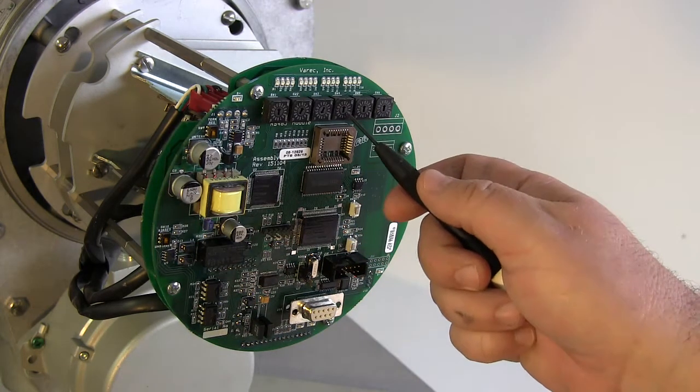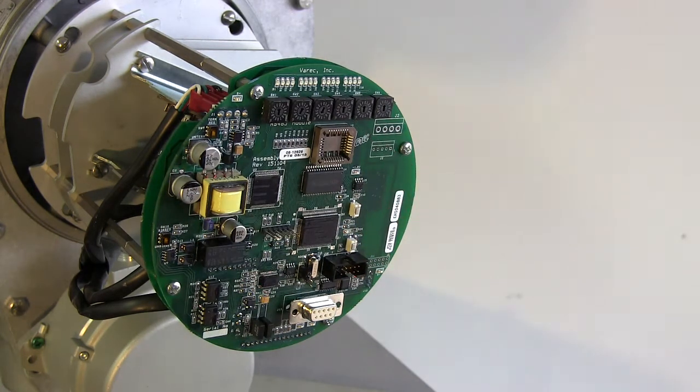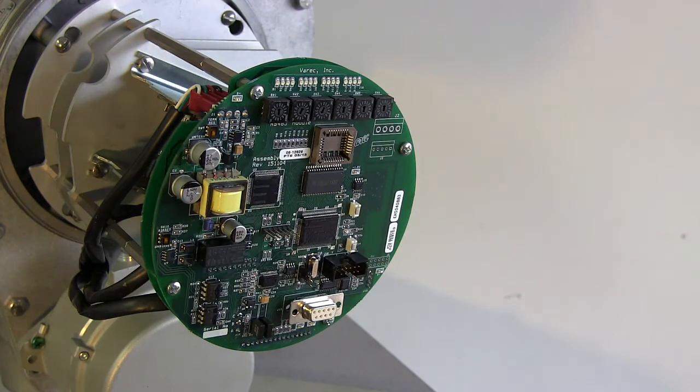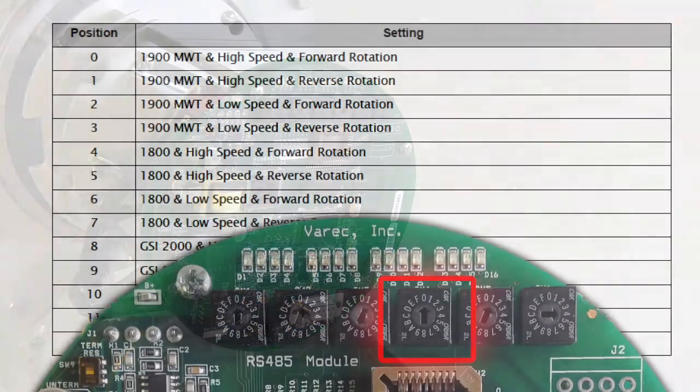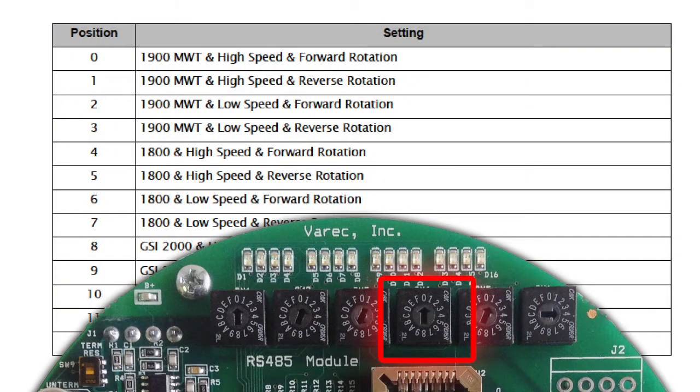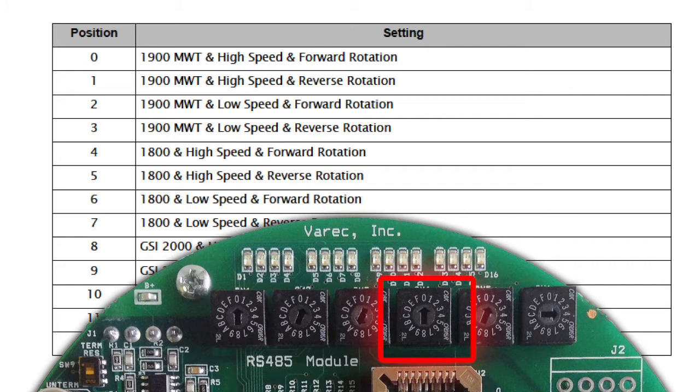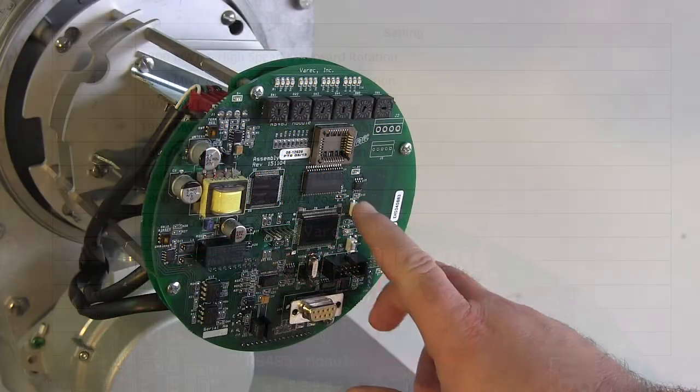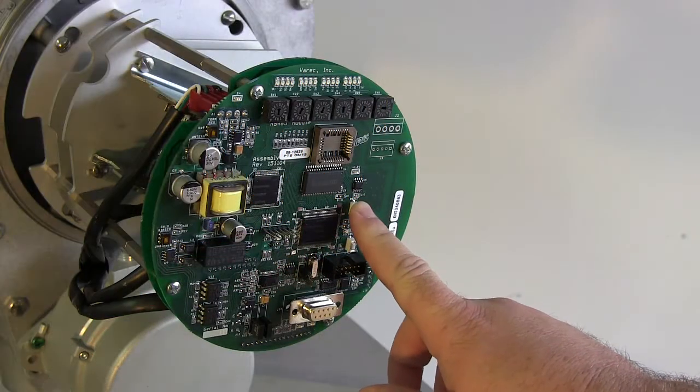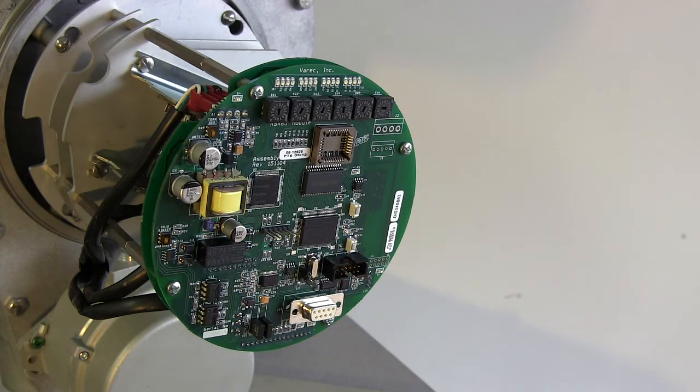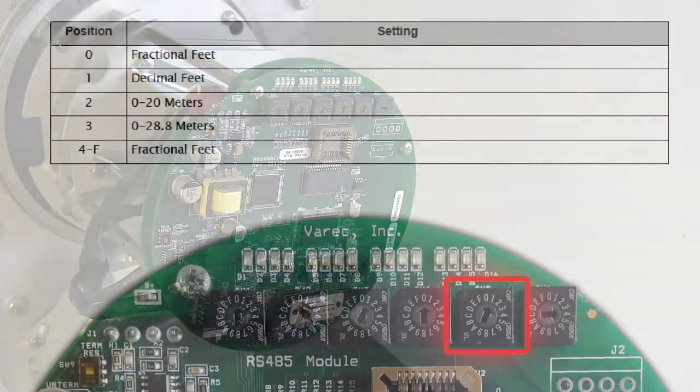Next, we use SW4 to choose the communication setting. Ours is a replacement for a Varec 1900 MWT transmitter with high speed communications and forward rotation, position 0, most cases for a Varec 1900. But check the table in the 2910 manual and select a position that matches the configuration of the unit you've replaced. Once the communication switch is set, press SW7 again to save the change and reset the CPU.